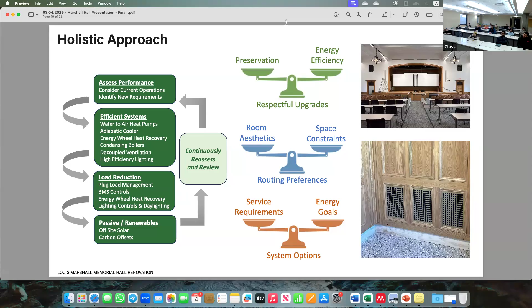So we wanted to have a cohesive system throughout the building. It was kind of a mismatch of what was there before. So the main system is a heat pump. What that means is that you have a bunch of systems throughout the building that have a fan and a compressor. And then those are all tied into a hydronic system that really fluctuates in temperature quite a bit. It's allowed to float. And then the heat pumps use the compressor energy to either heat or cool the building. So even though we have those natural gas boilers, we're really pulling some of that load off of natural gas and using the compressor energy, the electrical energy of those heat pumps, to heat and cool the spaces.